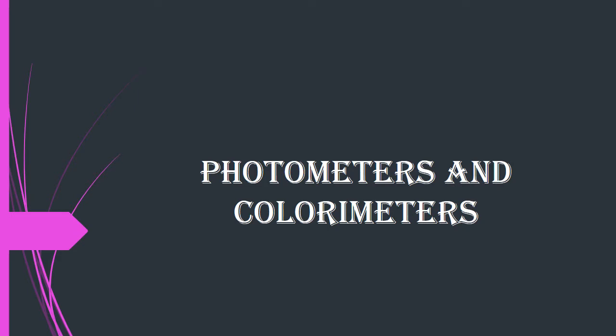The basic principle behind this colorimeter is that many chemical compounds in solution appear colored, with the saturation of the color depending on the concentration of the compound. Hence, the concentration of the substance can be determined by transmittance T, and the absorbance or the optical density can be given as A. By measuring the optical density or absorbance A, the concentration of a given substance in the sample can be determined. Colorimeters can be a filter photometer or spectrophotometer. So, let us now move on to the types.